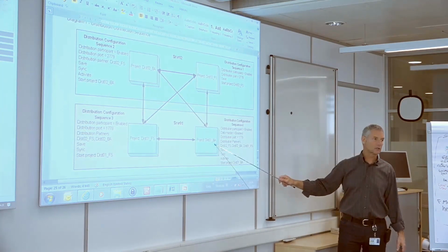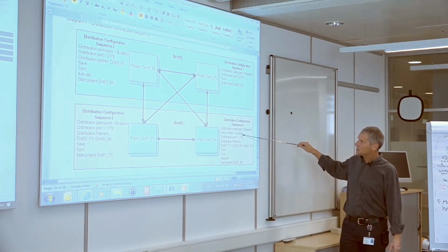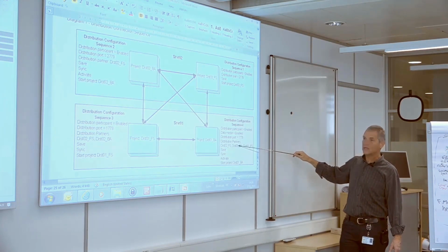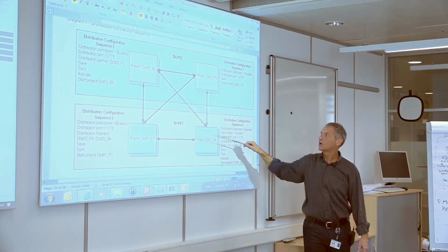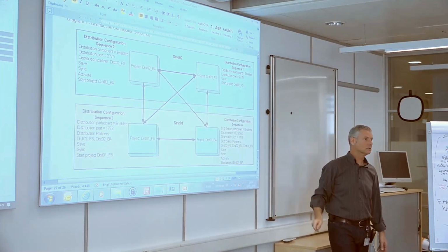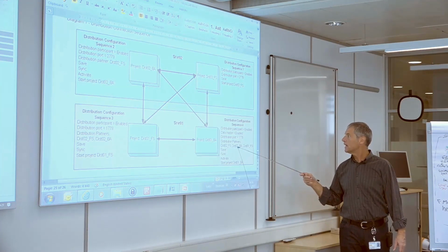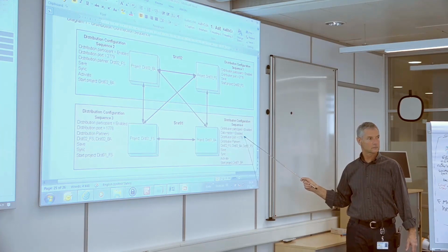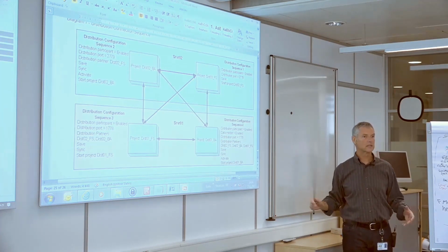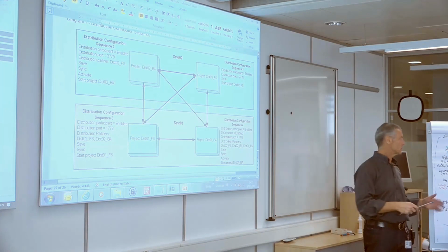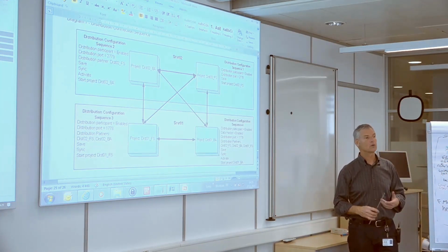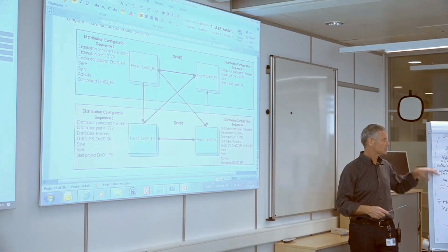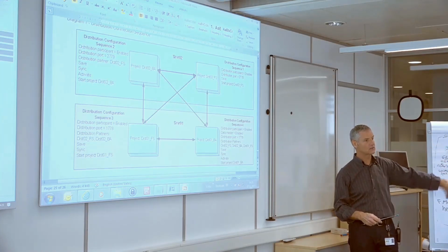From the BA project on the first server, exactly the same steps. Now I have to make 3 connections. So I'm pointing to here, here, and here, all bidirectional. And I'm going to make it the data master. One project has to be the data master, because when we do the configuration of these global users, they will get replicated. Global users, groups, event schemas, a lot of things are being replicated from the data master downward.